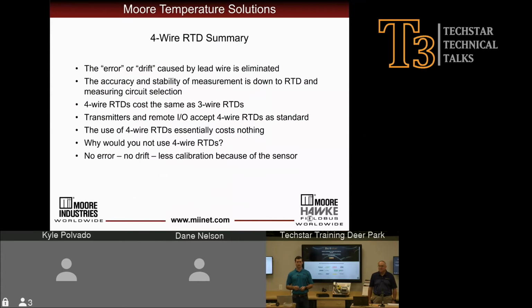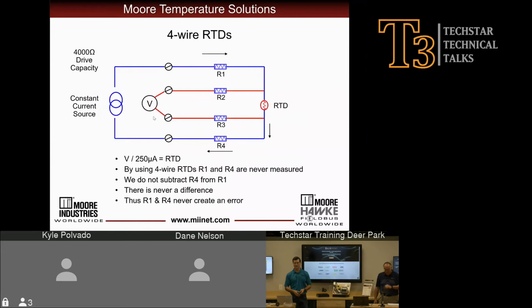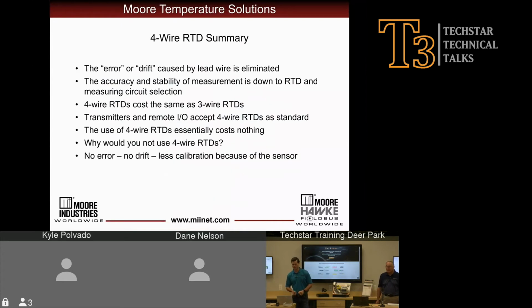So just kind of going back over 4-wire RTDs, the error or drift caused by lead wire is eliminated by using a 4-wire RTD. Again, we're only taking the resistance in the resisting element, which is telling us the temperature. So there's no longer any compensation being taken from R1 or R4. The accuracy and stability of the measurement is down to the RTD and the measuring circuit selection. Most don't know this, but 4-wire RTDs cost about the same as 3-wire RTDs. And it's important when ordering RTDs to specify if you want a Class B or Class A sensor. Most manufacturers, by standard, will send you a Class B RTD sensor. You might have to specify a Class A sensor.